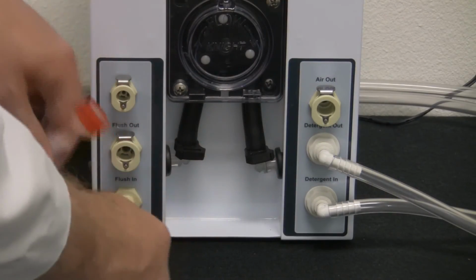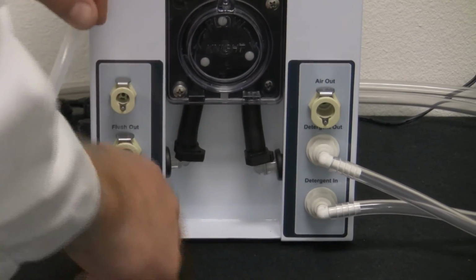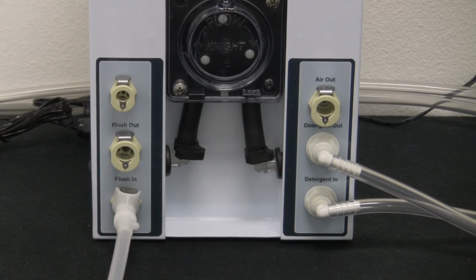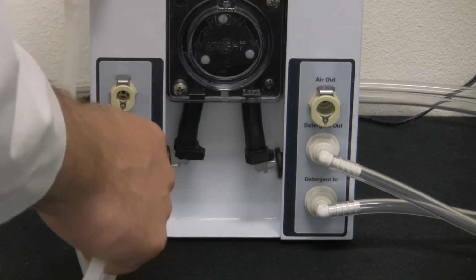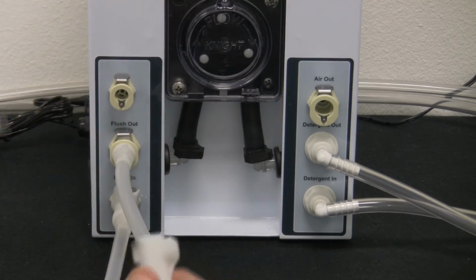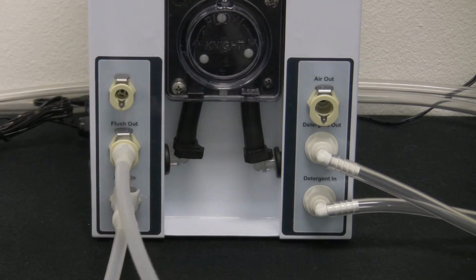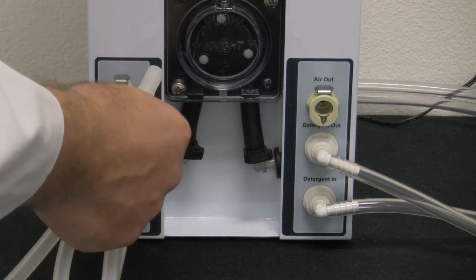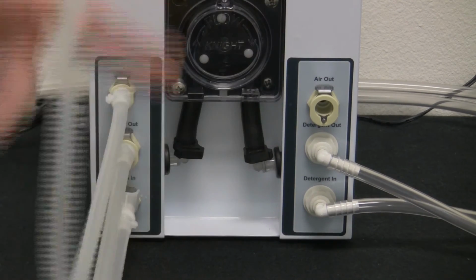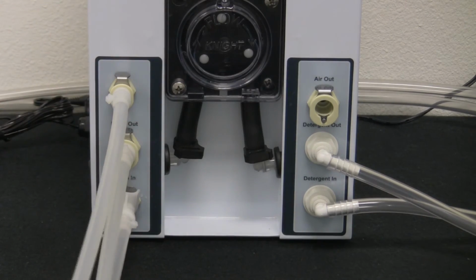Next, locate the flush suction tube and attach it to the fitting labeled Flush In on the ScopeTech IQ. Locate the flush discharge tube and attach it to the fitting labeled Flush Out on the ScopeTech IQ. Attach the flush discharge tube extension to the flush discharge tube. Attach the auxiliary flushing tube to the fitting labeled Auxiliary Flush Out.